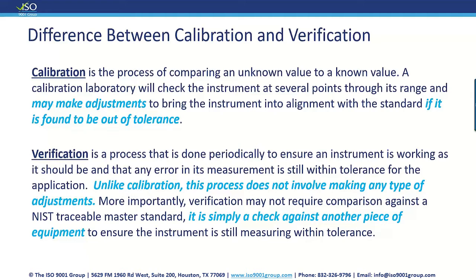So verification is a process that is done periodically to ensure an instrument is working as it should be and that any error in its measurement is still within the tolerance for the application and what you're using it for. So unlike calibration, this process does not involve making any types of adjustments. More importantly, verification may not require comparison against a NIST standard. It is simply you checking against another piece of equipment to ensure that your instrument or your device is still measuring within tolerance, right? You can do that in-house. In many cases, you can do that in-house. Maybe you have some sophisticated equipment that you may not be able to do in-house, but I can guarantee you there's a lot of equipment that organizations can verify as opposed to sending it out for calibration. I mean, let's think about this for a second.